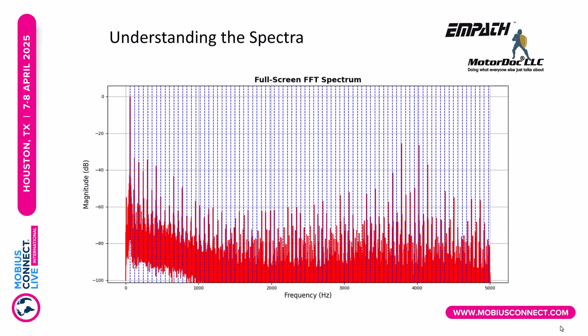This is a larger spectra. I know it looks a little noisy. The vertical blue lines, those are actually line frequency. So what you often do when you take a look at something like this is you will want to see what are basically harmonic peaks and what are fault peaks. So you will notice that there's a primary peak. The peak is at 0 on the far left. That's because we're going to count from the top down to peaks. So when you see dB down or minus dB, that's because we're counting from 0 down towards whatever the peak is. So the highest noise, if you want to think of this in terms of sound, the highest pressure or highest noise, highest force is going to be at line frequency.